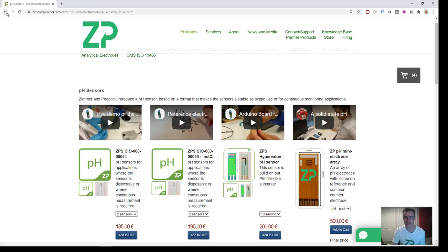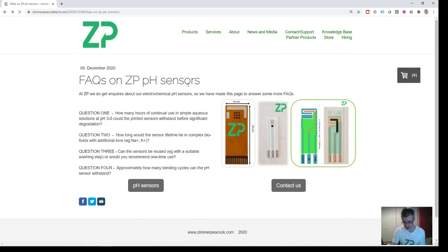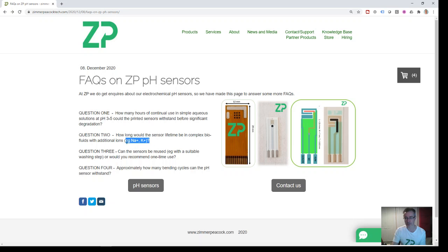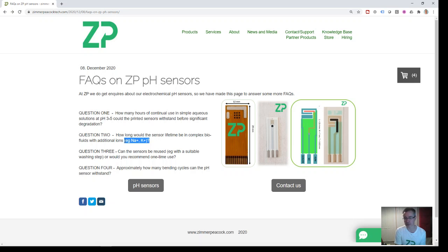Now, these sensors are asked: can we use it with sodium and potassium present? Obviously with things like phosphate buffer solution—which I understand is not a complex medium—we do have sodium and potassium in the buffers, and they don't interfere with the pH sensor.